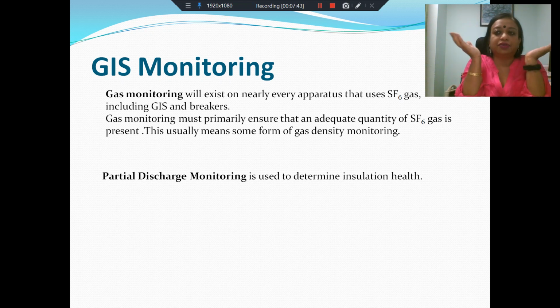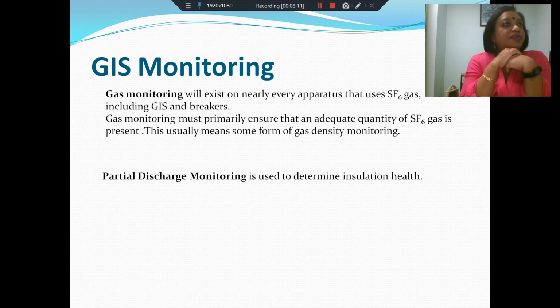Apart from other monitoring that will of course take place, a very important and very extensive monitoring that we need to do in case of GIS is partial discharge monitoring. Now, I did mention that SF6 has a higher dielectric breakdown strength. However, SF6 is also very prone to charge accumulation. So it's considered to be a brittle gas, in the sense that whenever you have local field enhancement, local discharges are very likely to happen. Therefore, PD monitoring is an advantage, because it will give us an idea about what is happening inside. We have a problem in GIS that we do not have access to what is happening inside, and PD gives us a good idea of any hazards, any insulation health deterioration that might be taking place. So extensive PD monitoring is done in GIS in order to monitor the health of the system.